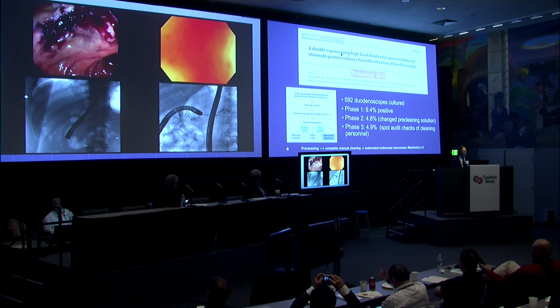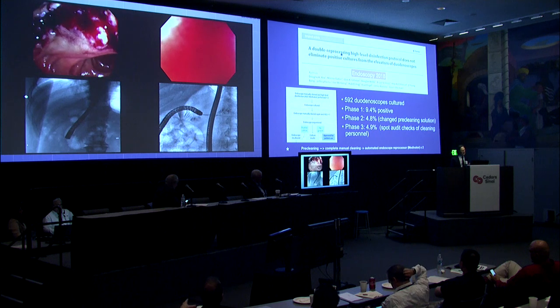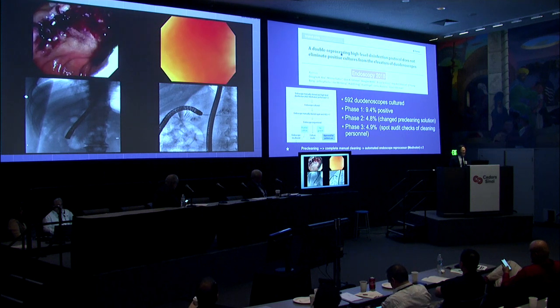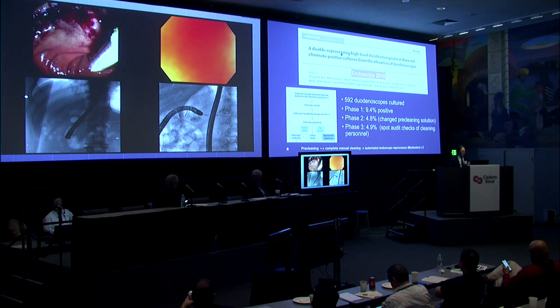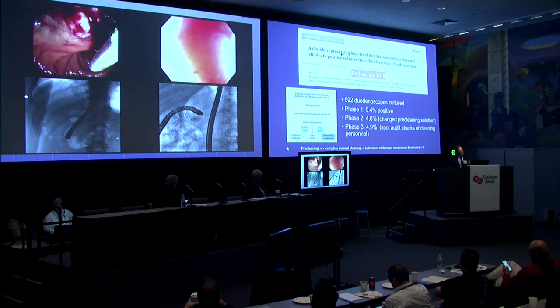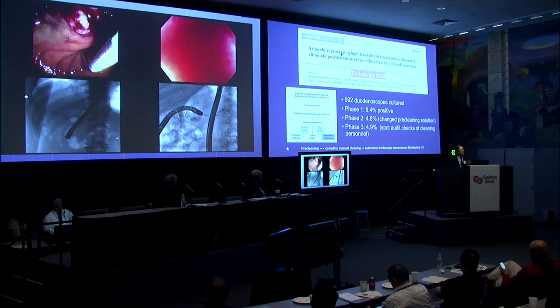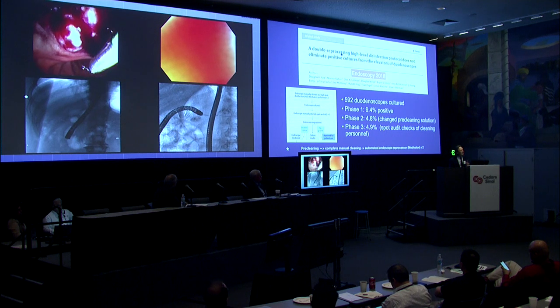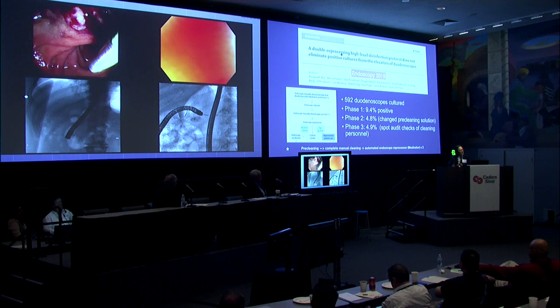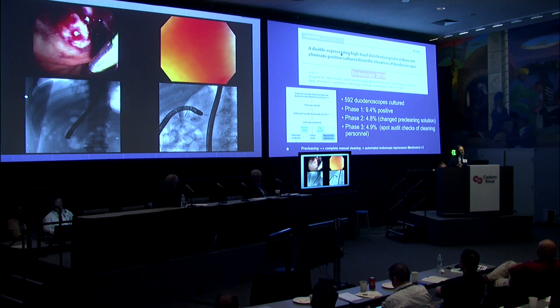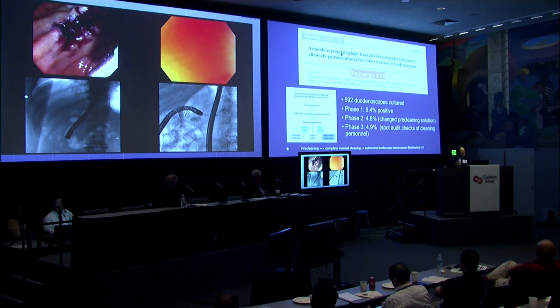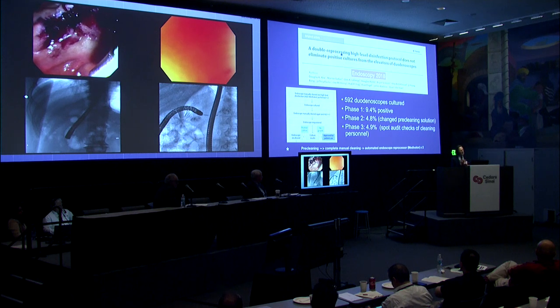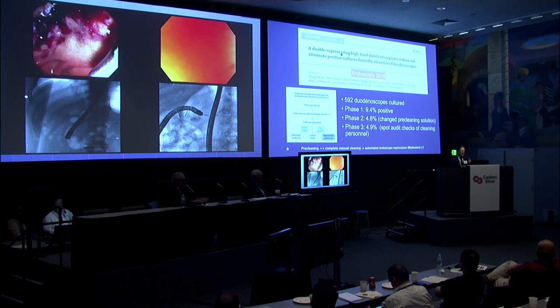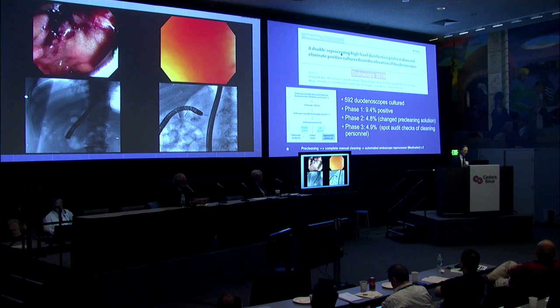Well, this is interesting. Doug Rex did a study with double reprocessing using high-level disinfection. When he started, 592 duodenoscopes were cultured, and the rate of contamination was 9.4% with double reprocessing. They cleaned the scopes beforehand, put them through the automatic endoscope reprocessor, and then did it again, and it came out at 10% positive. In phase two they changed some things, especially the pre-cleaning solution and how intensely it was administered, and the rate dropped, but it was still 5%, so still high.